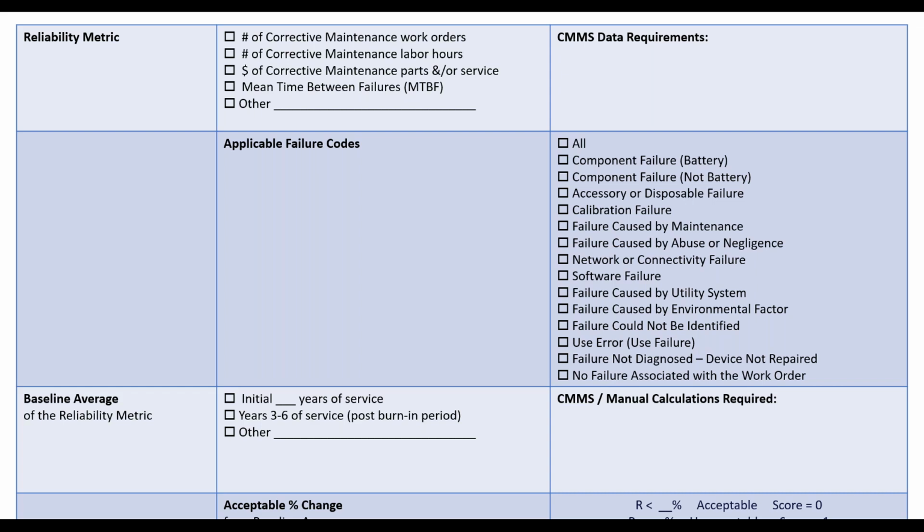Right. Like that. And then I snapshot this, let's say, into the post warranty. Okay. Right. So that's built into the cost of the machine. Right. So how many years post warranty though? Because remember, this is our baseline, and we're going to measure against it. So once I start paying for the repairs, that's when I start measuring what those repairs cost.